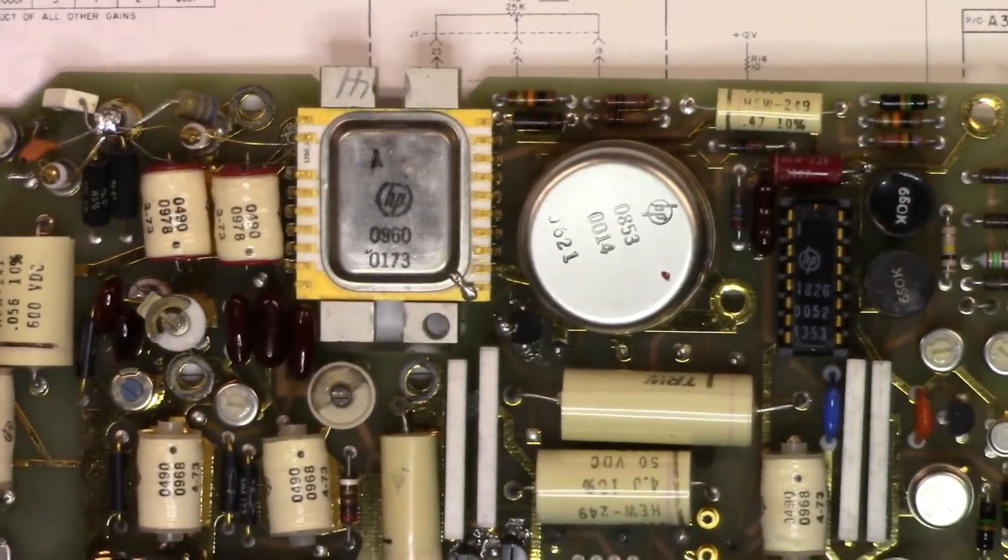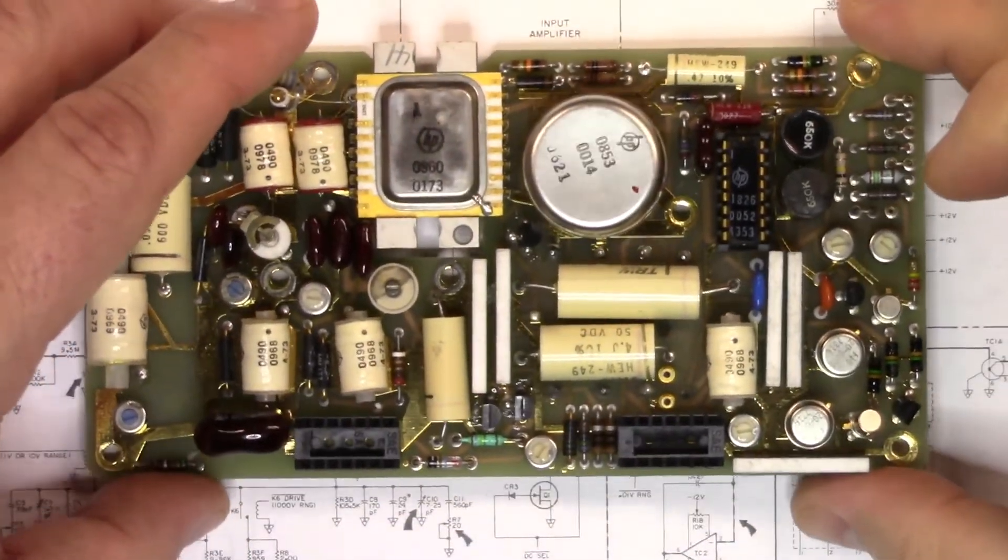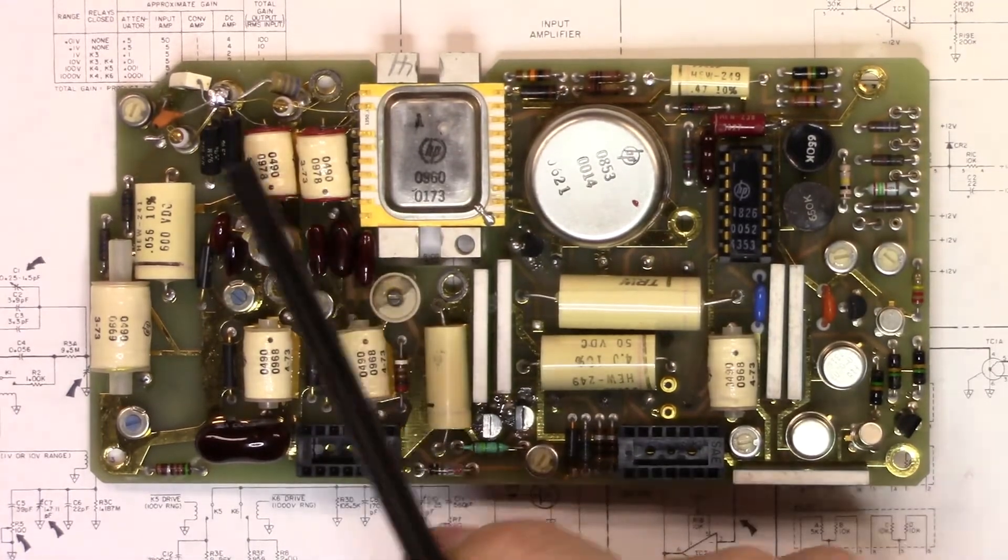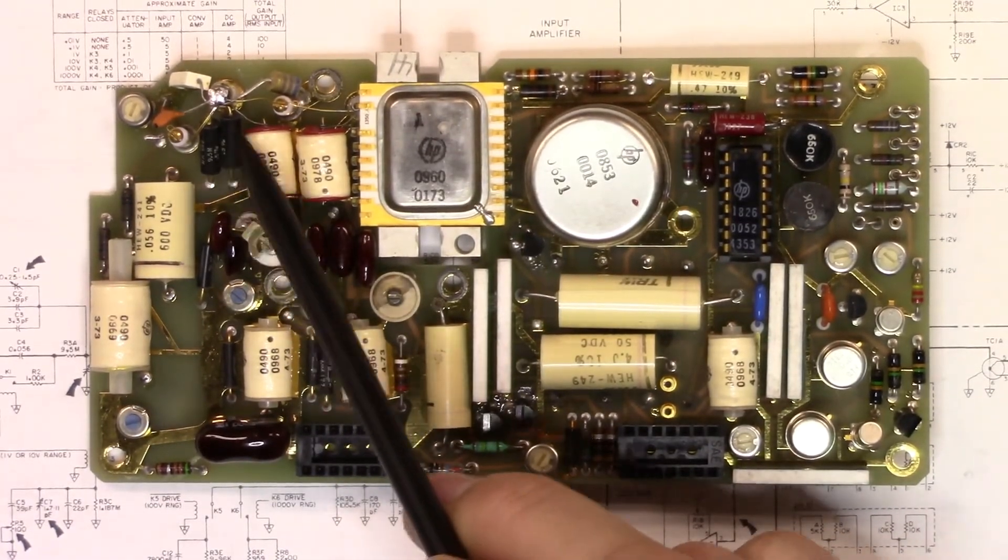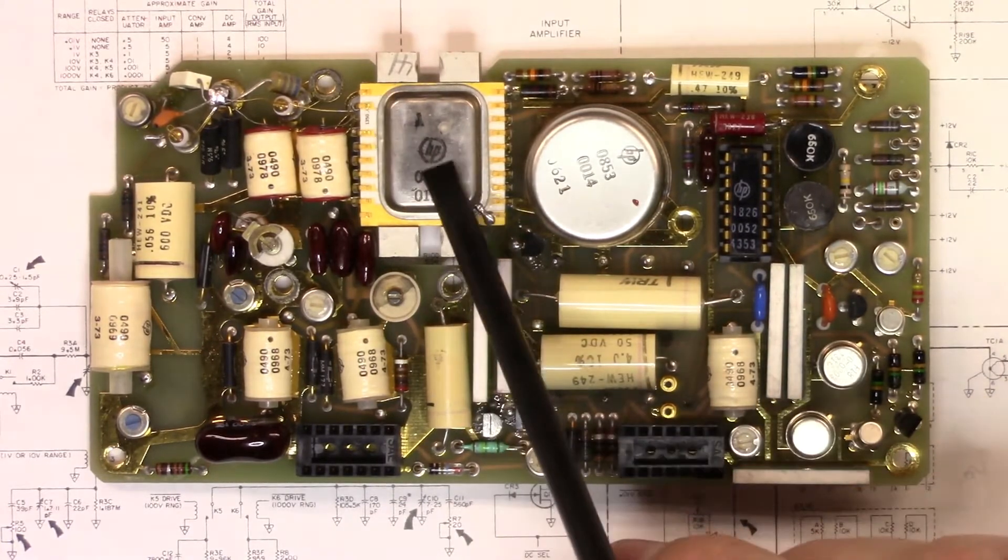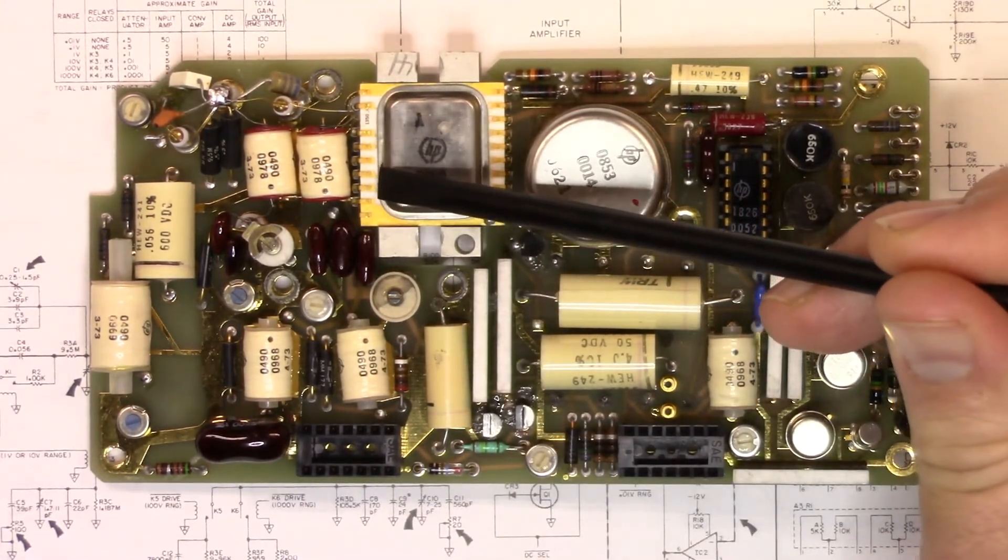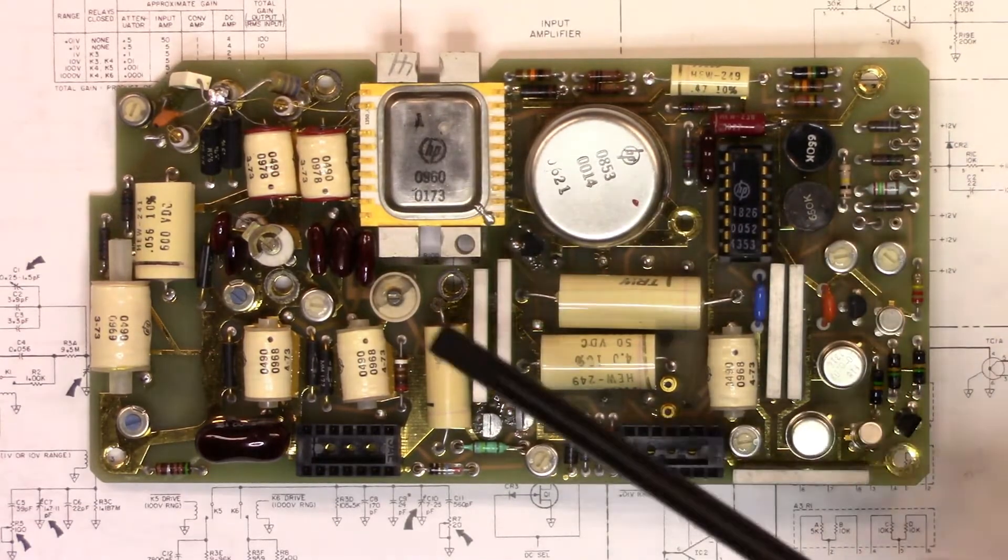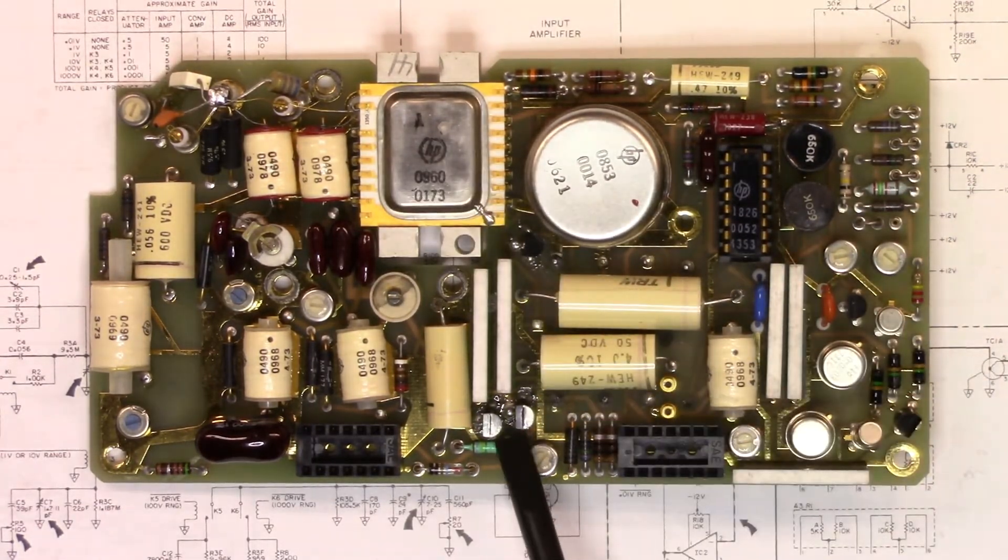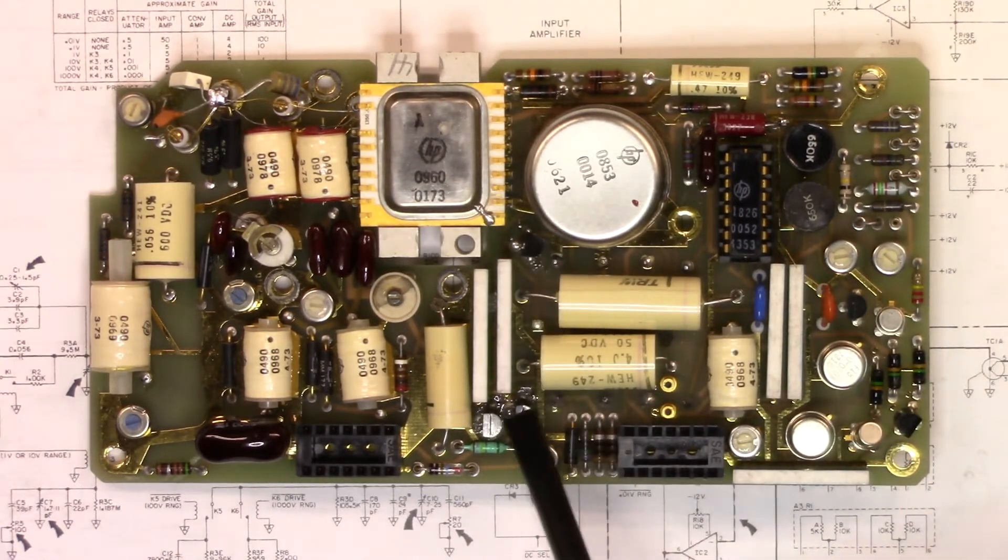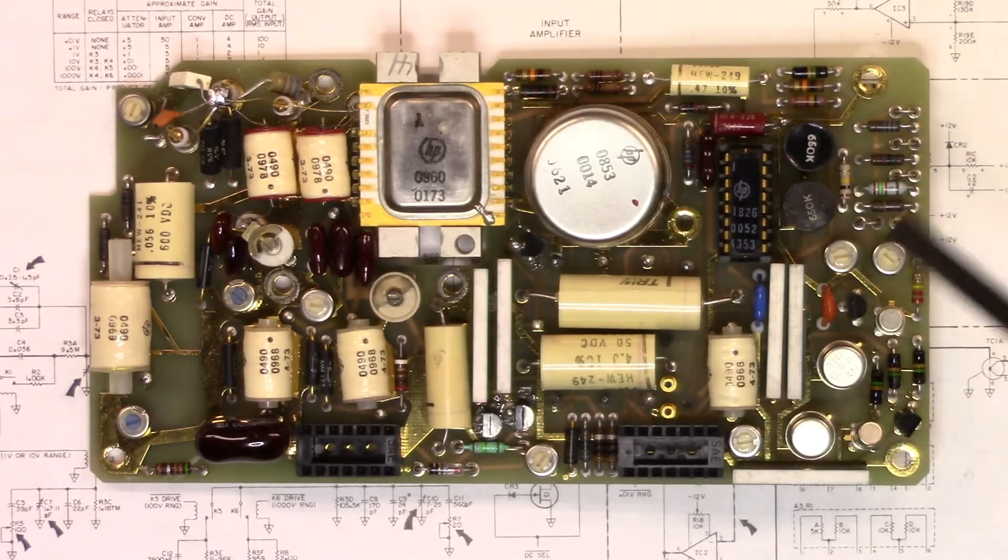Now you see the board here. The attenuator section is this part over here and you can see there are the two 9.5 meg resistors. That comes into pin one of the input amplifier here. Then pin six and seven are just here and that has our power on it, which is controlled by Q4 and 5 here and Q6 here, which will turn those rails on and off.